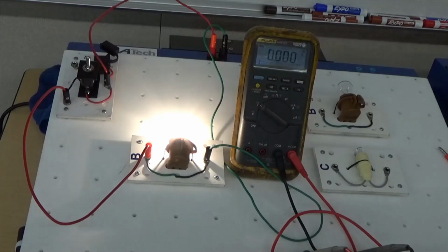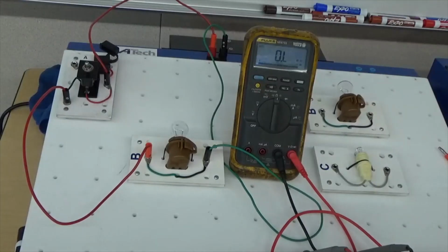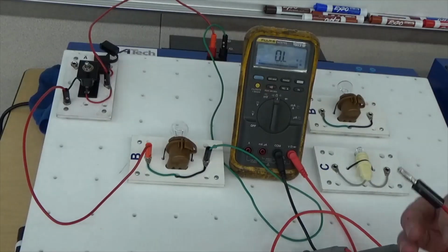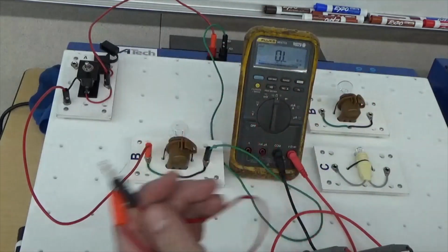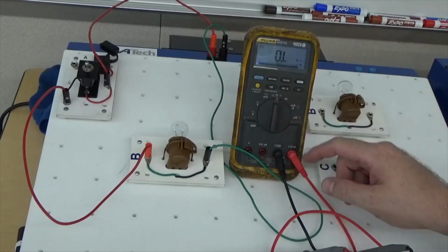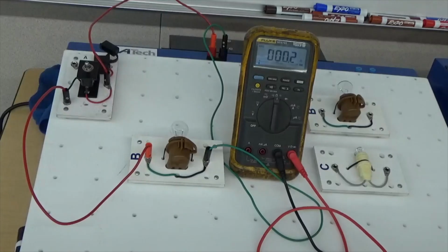Now, let's check resistance. Turn our meter to resistance right here. We turn power off. Whatever it is you're going to be measuring, you have to make sure that it is free of any power input. Because this meter has a power supply, a fuse, a control switch, and its own circuit pathway, whatever you're measuring becomes the load in its own private series circuit. The meter is going to send a little micro amount of voltage through it to precisely check the amount of resistance this has.